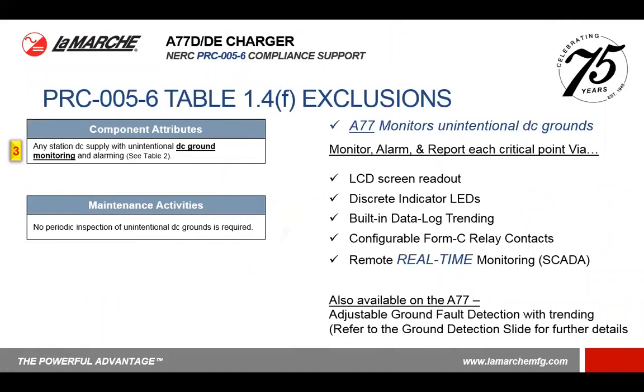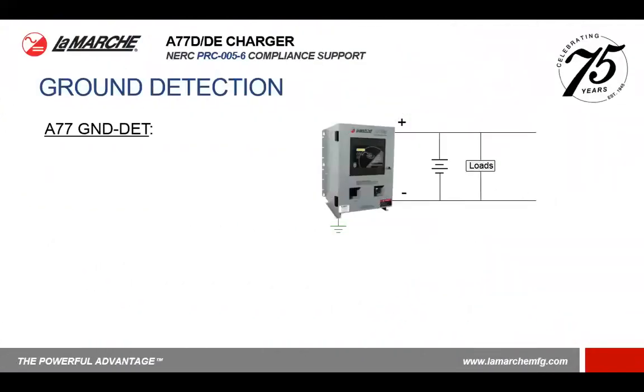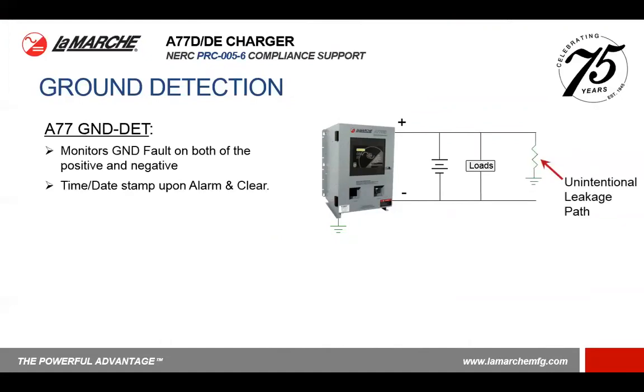Let's look at DC ground monitoring, point number 3. Well, the A77 also monitors for unintentional DC grounds. Within a standard DC system, normally at a substation, you'd have a floating DC system. And when there's an unintentional leakage path, it's necessary that the charger monitors for this. So on the standard A77, we can monitor for ground fault on both the positive or the negative, write a time date stamp when the alarm occurs or when the alarm clears. We can indicate via relay contacts that might be monitored by an RTU, as well as sending a message out over SCADA to a remote monitor.